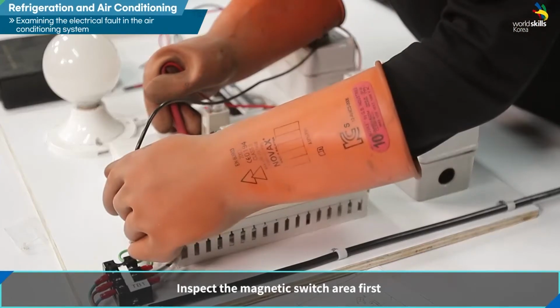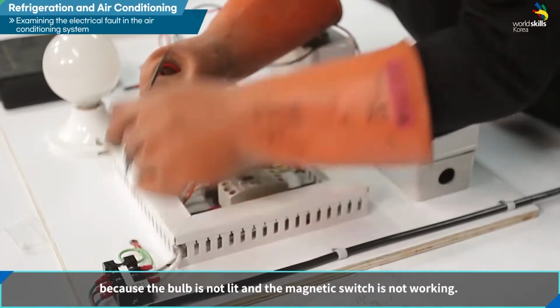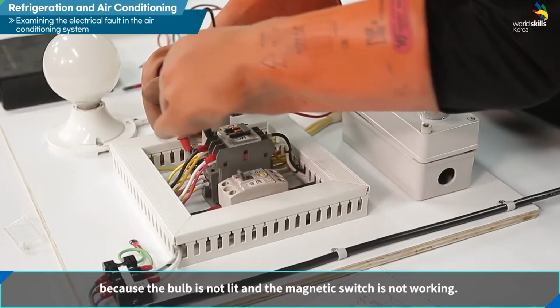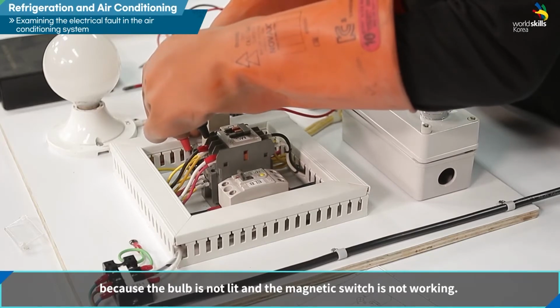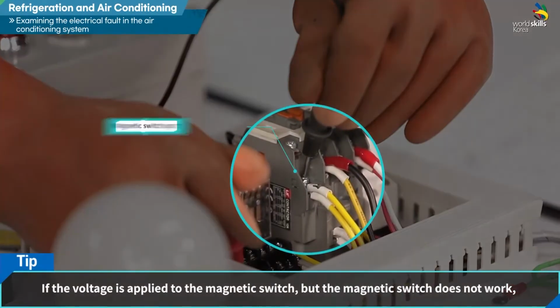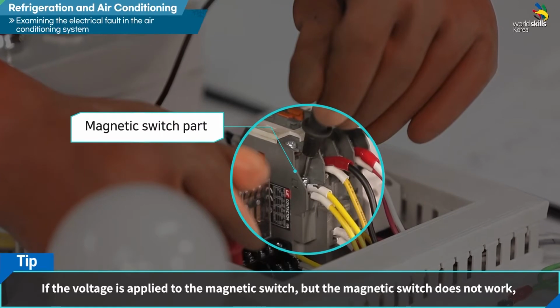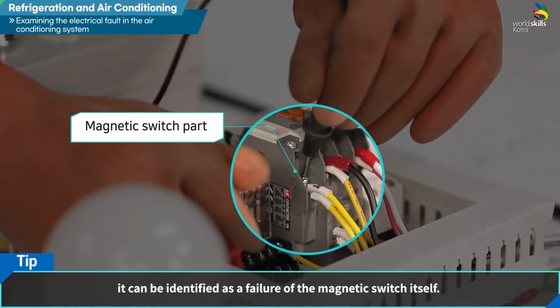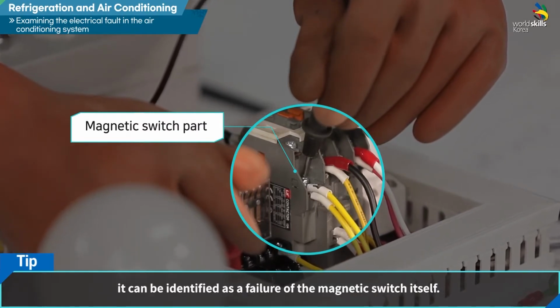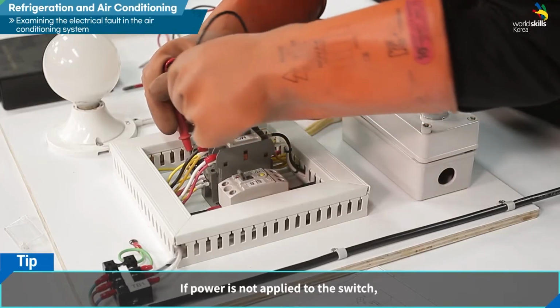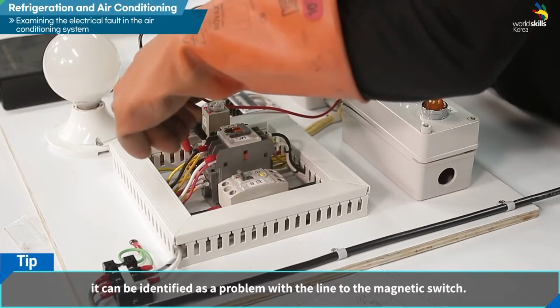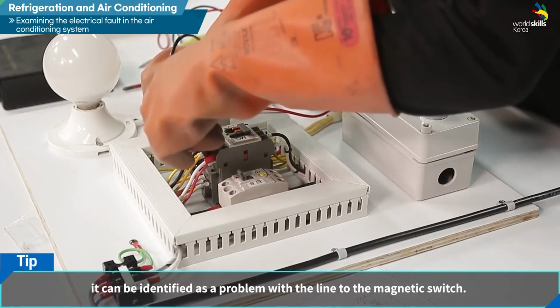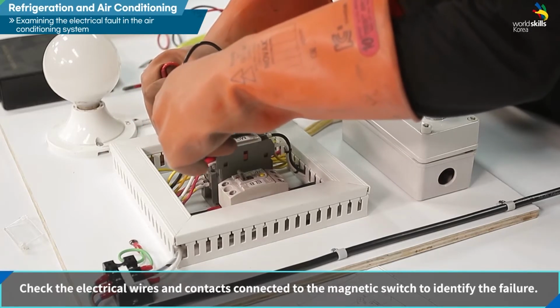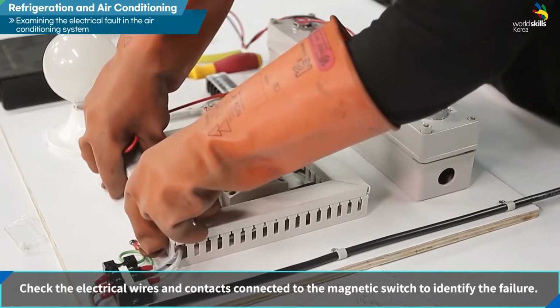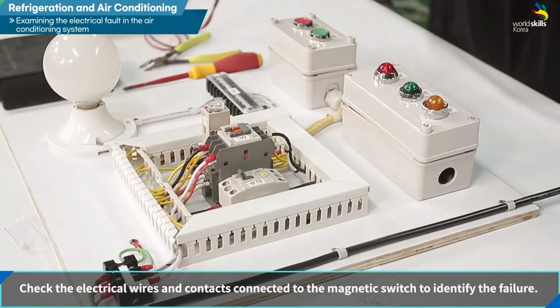Inspect the magnetic switch area first because the bulb is not lit and the magnetic switch is not working. If the voltage is applied to the magnetic switch, but the magnetic switch does not work, it can be identified as a failure of the magnetic switch itself. If power is not applied to the switch, it can be identified as a problem with the line to the magnetic switch. Check the electric wires and contacts connected to the magnetic switch to identify the failure.